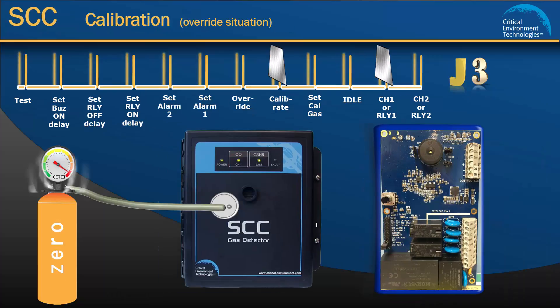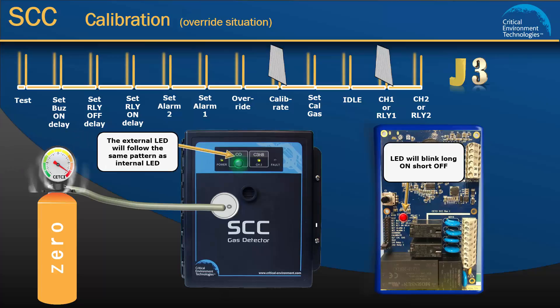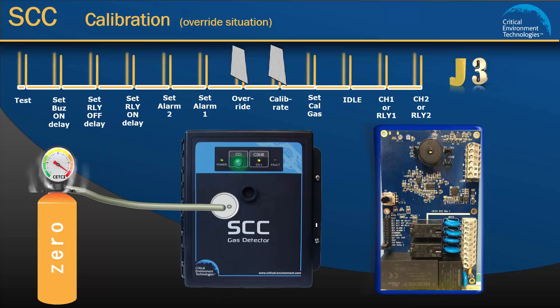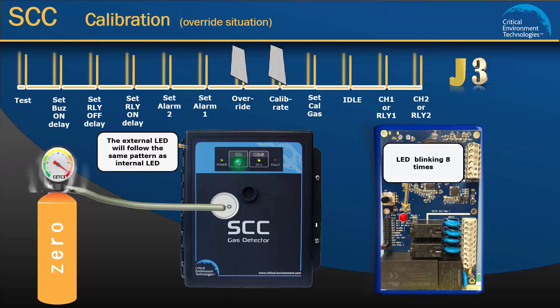If the sensitivity of the sensor is calculated to be out of range for what can be compensated for during the null calibration, the internal LED and external channel 1 LED lights will blink a pattern of long on and short off, and you will need to do an override. Leave the jumper on calibrate and move the jumper from channel 1 to override. This must be done within 30 seconds or the calibration will be cancelled and the unit will return to normal operation. If outside the override range, the fault LED will blink for 5 seconds and calibration will be auto-cancelled. If the override is successful, the internal LED and external channel 1 LED lights will blink 8 times. After using the override position, return the jumper to channel 1 and proceed with the span gas calibration.